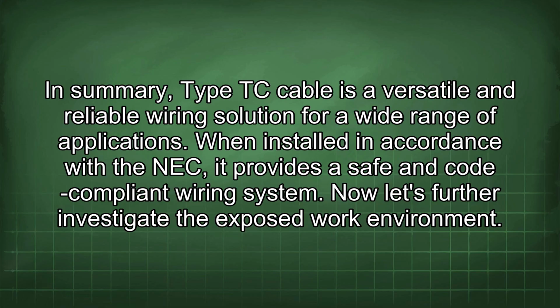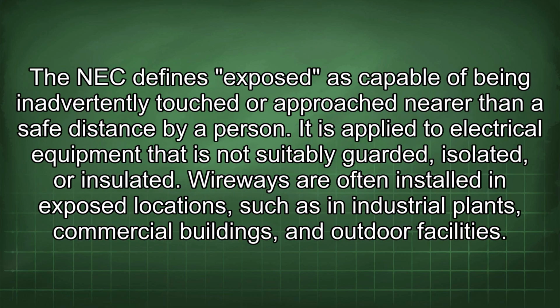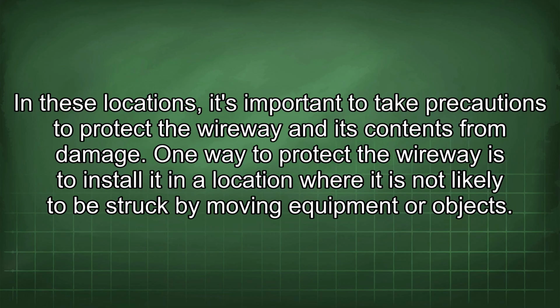Now let's further investigate the exposed work environment. The NEC defines exposed as capable of being inadvertently touched or approached nearer than a safe distance by a person. It is applied to electrical equipment that is not suitably guarded, isolated, or insulated. Wireways are often installed in exposed locations such as in industrial plants, commercial buildings, and outdoor facilities. In these locations, it's important to take precautions to protect the wireway and its contents from damage.